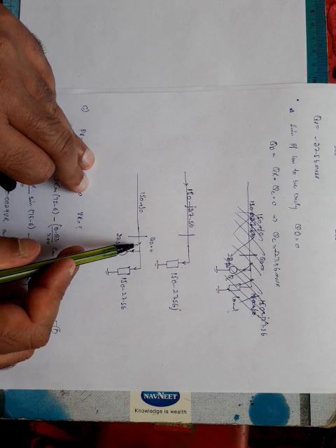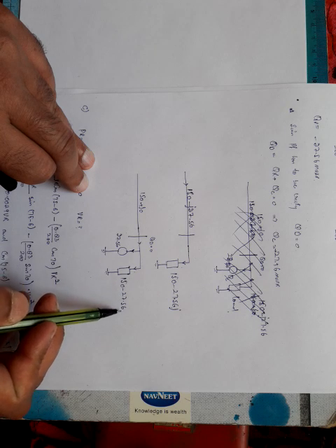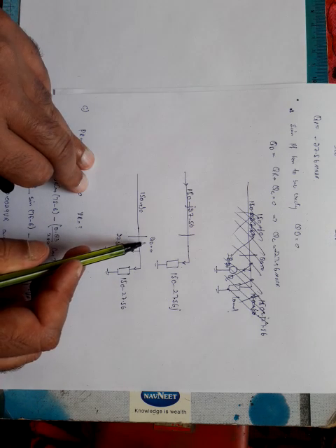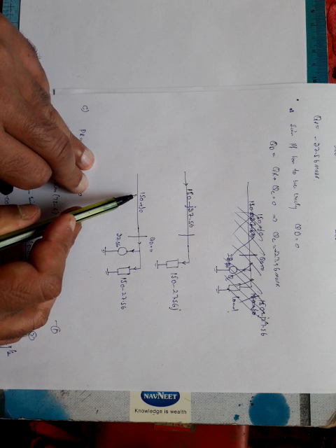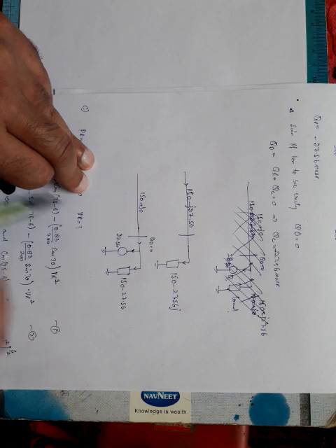You can just see that when we add these two, it will be 150 minus 27.56 plus 27.56, so that this QD is equal to 0. The power now supplied will be only real power, and we can say that the power factor is unity.